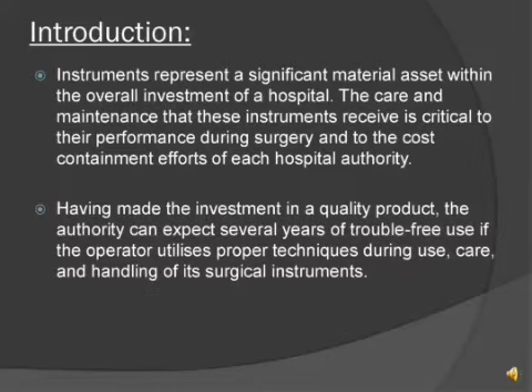The surgical instruments are made up of some materials. The first one is stainless steel. Stainless steel is used for surgical instruments. It is a 400 series alloy material we have to use in surgical equipments. It has several useful properties, and it can be brought to a very sharp cutting edge which will hold this edge through continuous use. It has a high tensile strength enabling it to maintain precisely set jaw approximations.